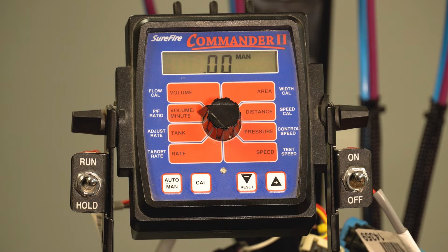In this test mode, we will run the pump. We can speed it up, slow it down, and during these tests, we really like to observe flow in volume per minute, in gallons per minute. We can check the pressure. This is really just a great way to go in and make sure that the system is working, and to winterize your system at the end of the year.